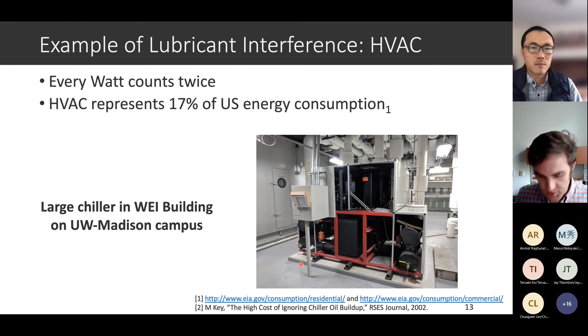And those journal bearings, again, require lubricant, and the lubricant inevitably leaches out into the refrigerant of the system and ends up coating the heat exchange pipes. When it does that, it decreases the thermal transfer, it decreases the ability to draw heat through those heat exchangers, which is exactly what you don't want to have happen. You have a heat exchanger to exchange heat. And so this is a fairly large problem.